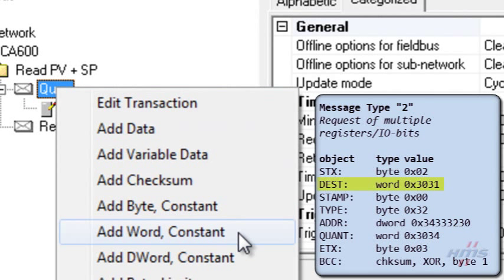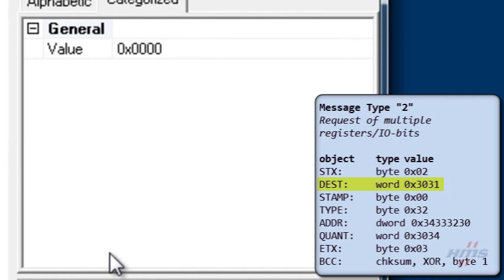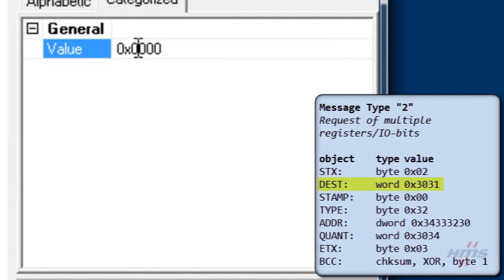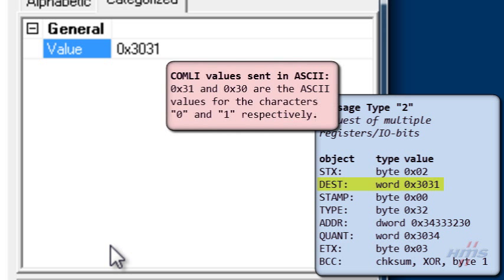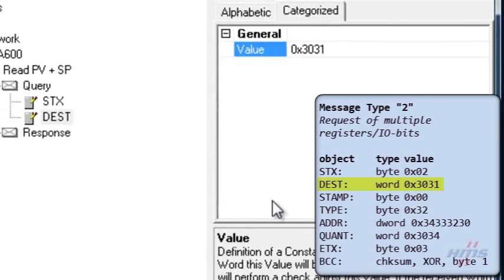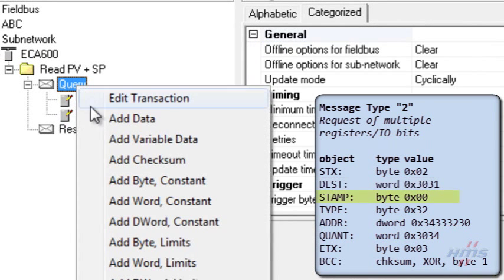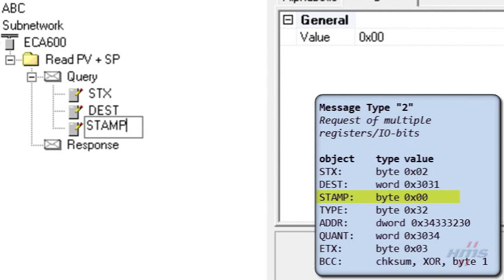Then we add a constant word for the destination object. We set the hexadecimal value to 3031, meaning node address 1. Then we add a constant byte for the stamp object and leave the value at 0, since the stamp object functionality is not implemented in the ECA regulator.